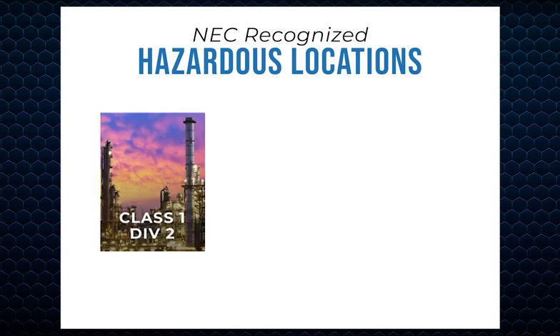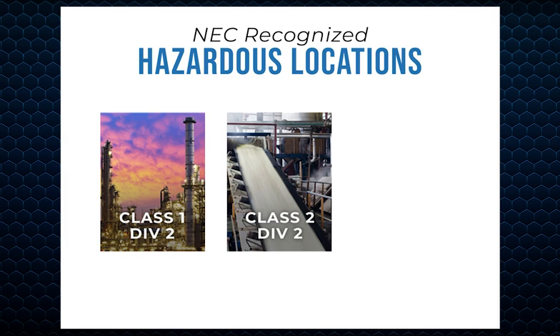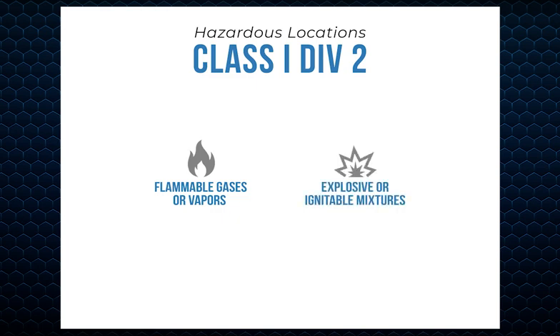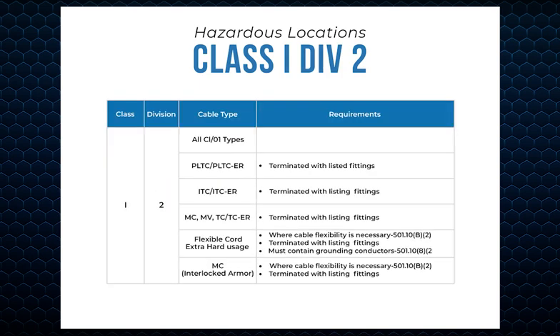The three hazardous locations to consider when selecting the right tray cable from Service Wire are Class 1 Div 2, Class 2 Div 2, and Class 1 Zone 2. Class 1 locations are those in which flammable gases or vapors can be present in the air in quantities sufficient to produce explosive or ignitable mixtures. Class 1 locations are further subdivided into 2 divisions and 3 zones. Refer to the NEC for a complete definition and listing.